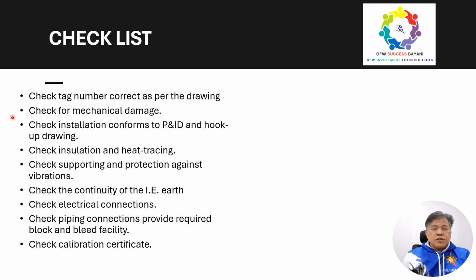Okay, check the installation that confirms the hook up drawings, any drawings, and check insulation and heat tracing if applicable. Heat tracing, because some of the pipes, some of the lines are hot, so that's why some instruments are used in that heat tracing area. So check support and protection against vibration, check the continuity, check electrical connections, check piping connections, check calibration certificate. So any calibration certificate should be stuck on our device.